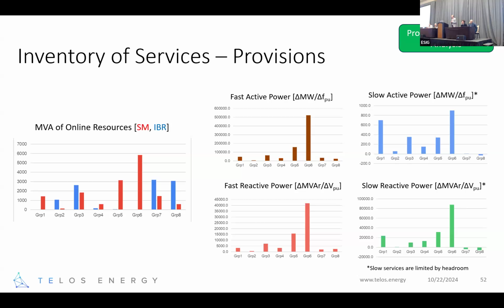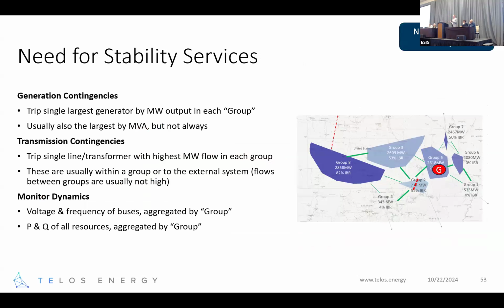You can see, for instance, groups 5 and 6 are largely comprised of synchronous machinery. You can also see, in the middle, with the fast active power and fast reactive power services, that there's the most provision there, and it looks similar to what you see from synchronous machinery. This is what we'd expect. Conventionally today, those fastest services largely come from synchronous machinery, not so much from the installed fleet of IBR, which is largely grid following. Of course, we know we're on the cusp of a substantial change there with the introduction of grid forming inverter technology, subject to how much it's adopted — hopefully a lot.